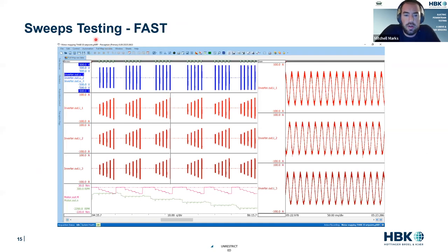Here's an example of a sweeps test where we have a fixed speed, and then we go through a variety of torques at that fixed speed, move to another speed, go through the torques, move to another speed, go through the torques. Here is 30 set points of voltage in blue, current in red, and then torque and speed in pink and green that we were moving through very quickly.